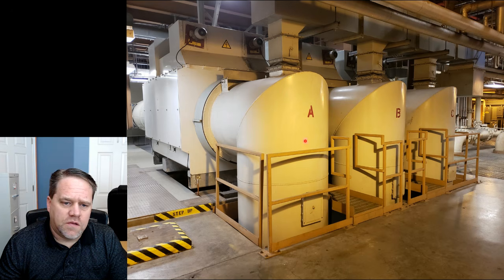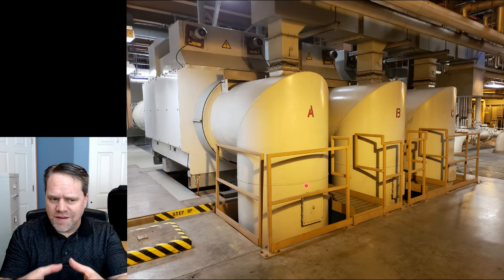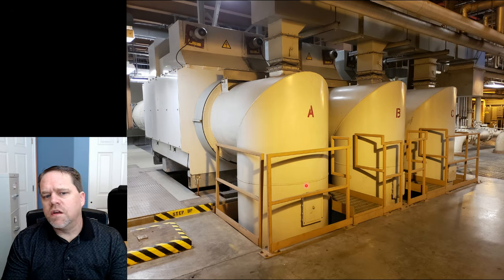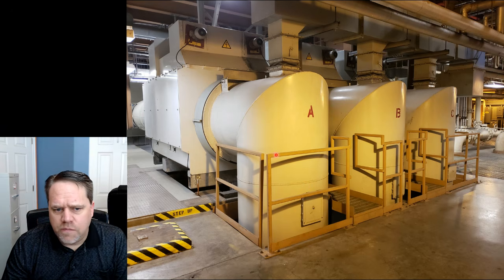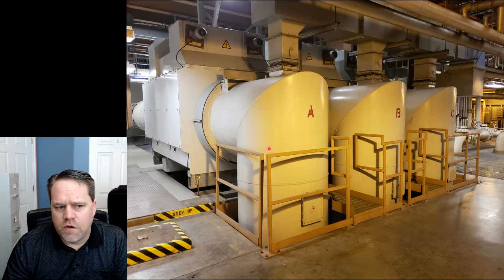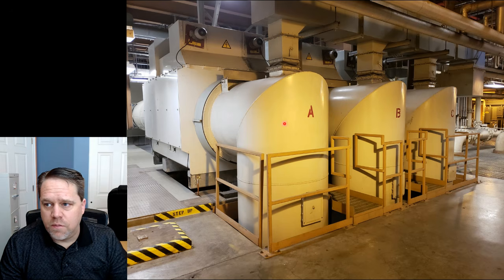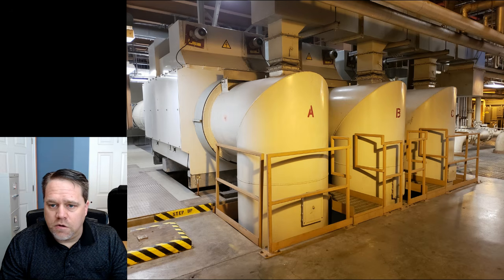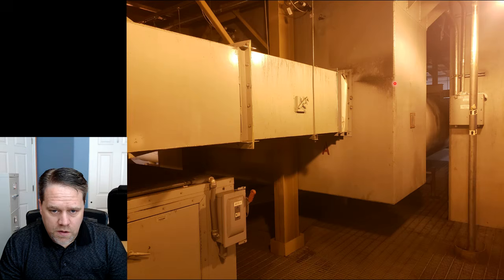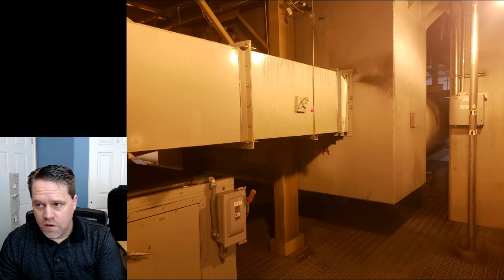Inside of each of these pieces of metal in these containers, I'm not sure what the material of them is. I'm guessing it's non-ferrous, but I'm not sure on that. But inside of these are hollow aluminum rods, and those are the actual conductors. So this would be phase A. If you're looking back here, it goes all the way through, and looking from the other side, that is that big square piece that you could see from the photograph, and then kind of a duct for those aluminum rods. And like we were saying, that is phase A, and there's three of those, phase A, B, and C. Phase A, B, and C go outside and they feed this bad boy. This is the transformer that takes our three-phase 26,000 volts, 20,000 or so amps, and changes it over.